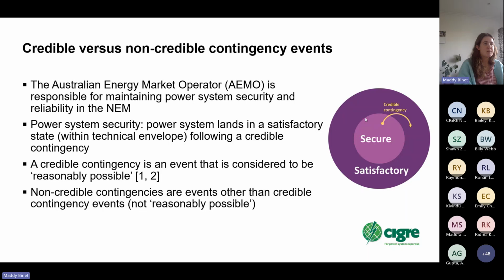This diagram shows the transition between secure and satisfactory. Satisfactory means the power system is within its technical envelope, or normal operating bands and limits - relating to frequency being within required bands, voltage within required levels, power flows on transmission lines in terms of thermal limitations of power system elements, fault levels, and stability or oscillations in the power system. All of those things have to be within their technical limits.